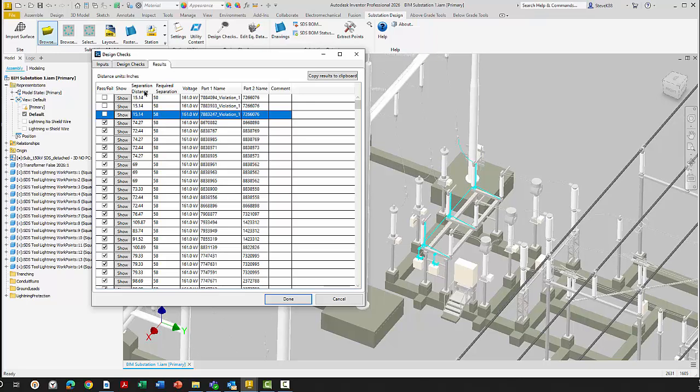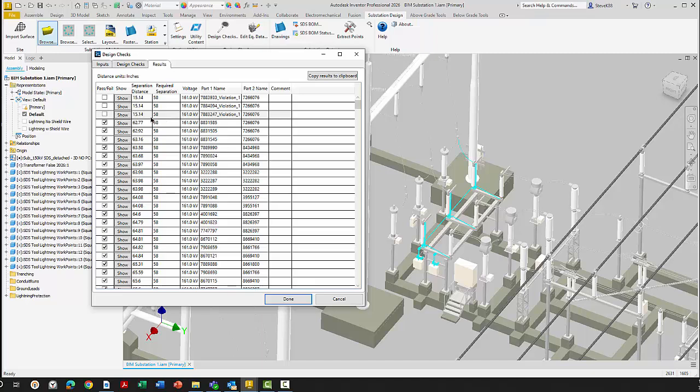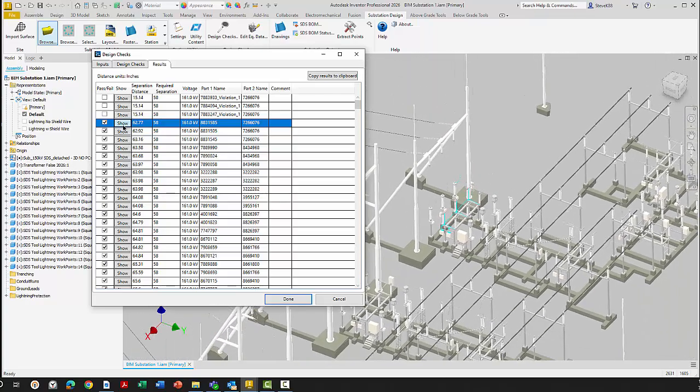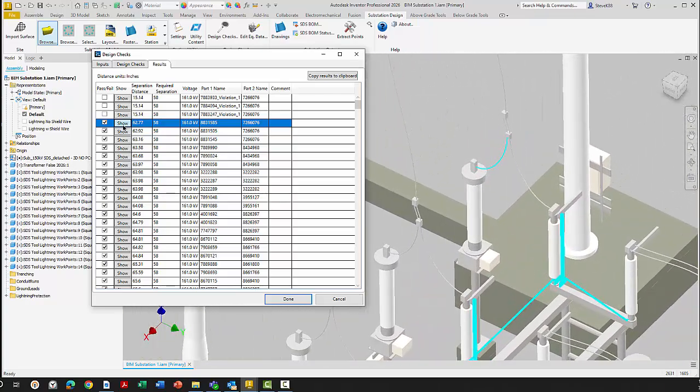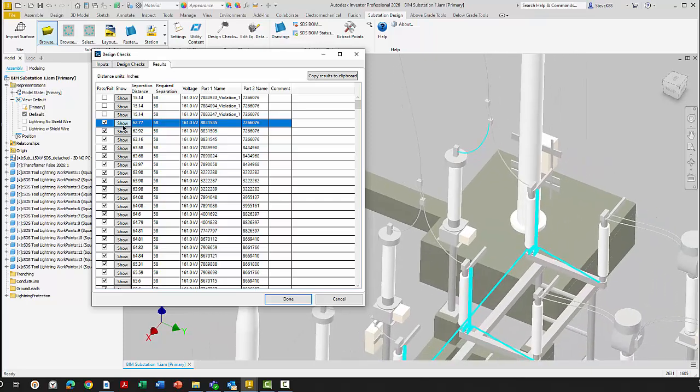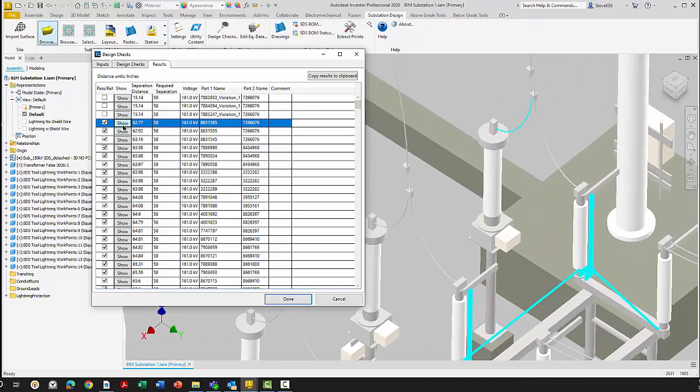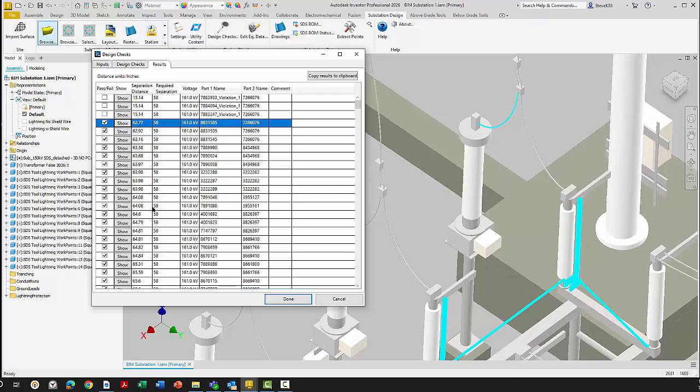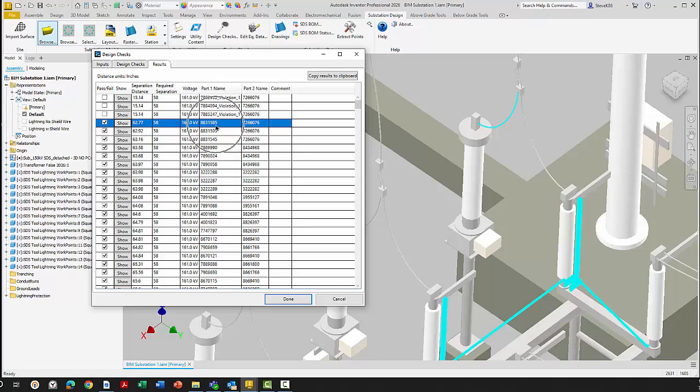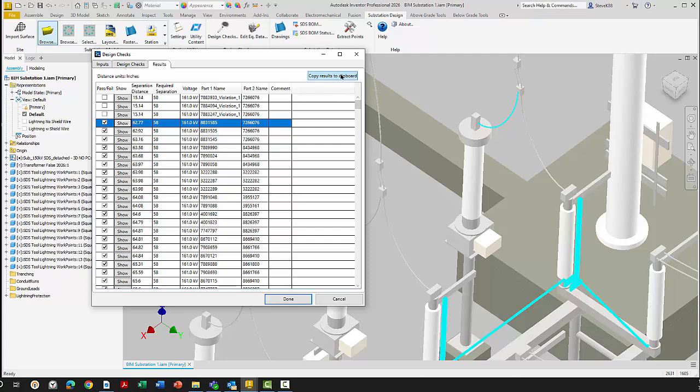We can also sort by the separation distance. The closest one is 62 inches on the 58. So let's go see what's on there. That's this one here. So that's the power going to the CCVT there. And it's close enough to the switch that it is close to failing, but it does not. We could search for any one of these. When you see the parts, you can search in Inventor and find what these parts are for a reference. This can be copied to clipboard and you have a record by placing it in Excel or Word or whatever your choice is. I'm going to say done and then we're going to run the other one.